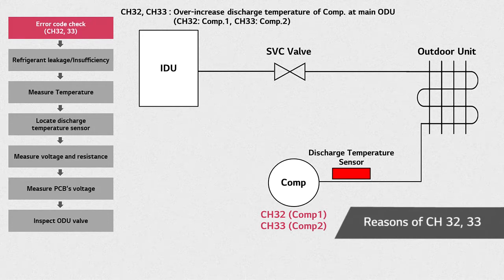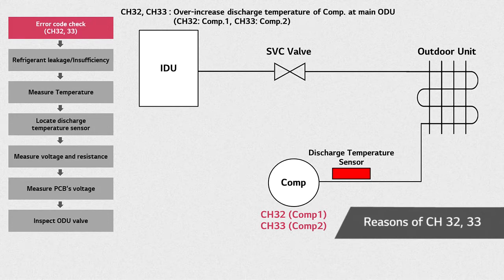The main reason for this rise in temperature is lack of refrigerant or leakage. As the amount of refrigerant goes down, it will take more heat. Also, damage in the discharge temperature sensor or damage in the EEV can give place to these errors.